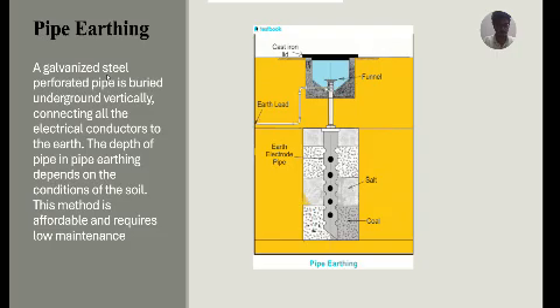In this method, we take a galvanized steel pipe and place it underground. This pipe is generally 2 to 3 meters long and it is vertically buried into the ground. This setup allows these excessive currents, or what we call the faulty currents, to be safely discharged into the earth or the soil. This method is highly affordable and requires very low maintenance. The depth that I've mentioned, 2.5 to 3 meters, usually depends on the type or condition of the soil.